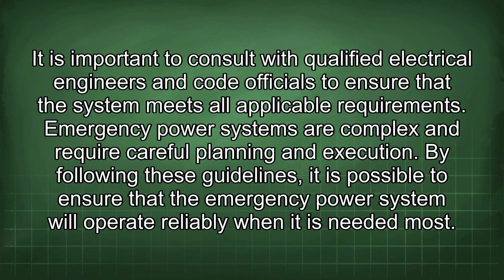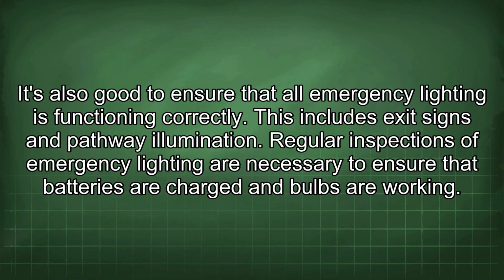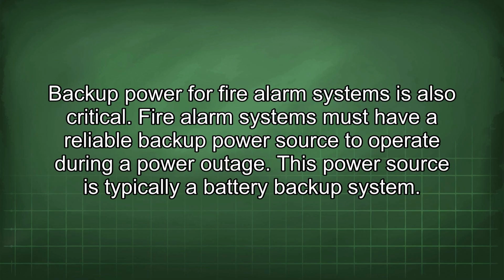It's also good to ensure that all emergency lighting is functioning correctly. This includes exit signs and pathway illumination. Regular inspections of emergency lighting are necessary to ensure that batteries are charged and bulbs are working. Backup power for fire alarm systems is also critical. Fire alarm systems must have a reliable backup power source to operate during a power outage. This power source is typically a battery backup system.